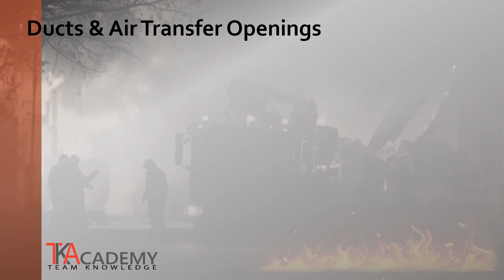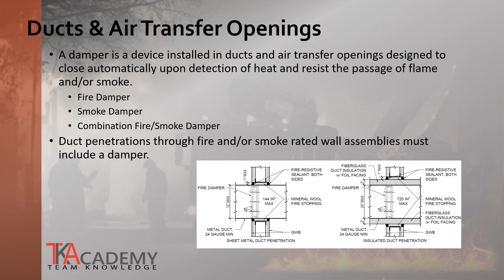In addition to doors and windows, there will often be ducts and air transfer openings within fire-resistant wall assemblies. When this occurs, a damper must be used. A damper is a device installed within the ducts or air transfer openings designed to close automatically upon detection of heat and resist the passage of flame and smoke. There are three types of dampers: fire dampers, smoke dampers, and combination fire-smoke dampers. Duct penetrations through fire and/or smoke-rated wall assemblies must include a damper with an equal level of protection rating.